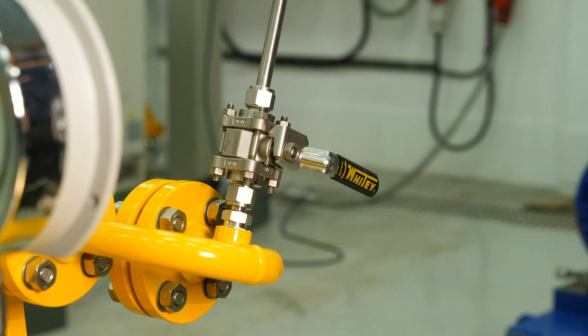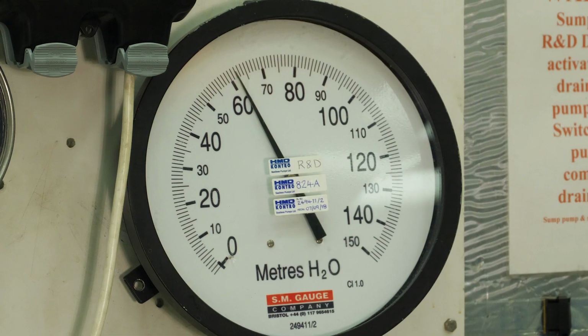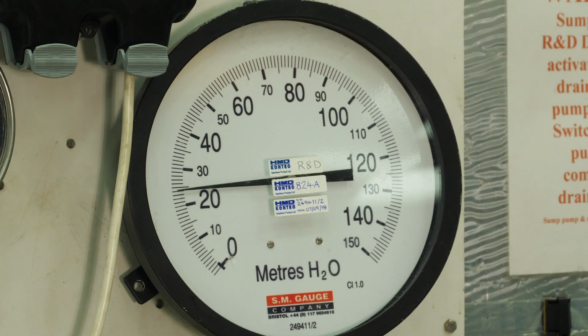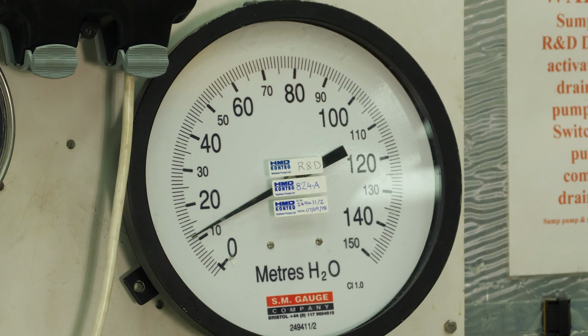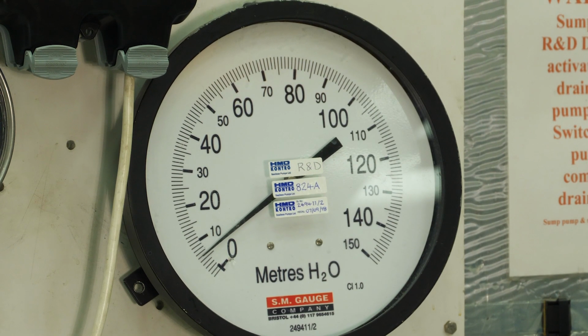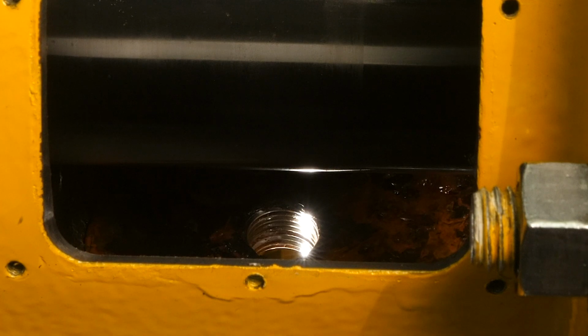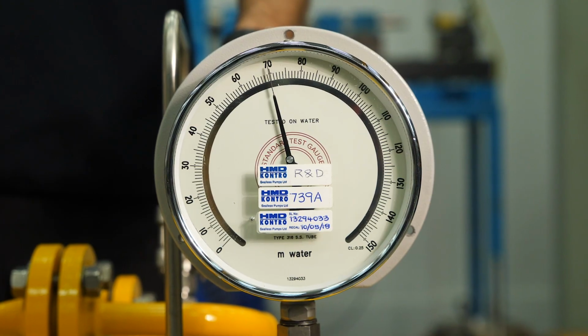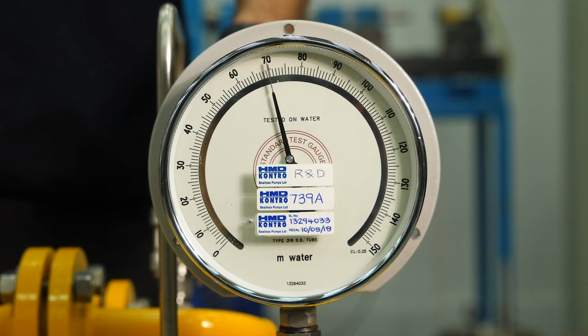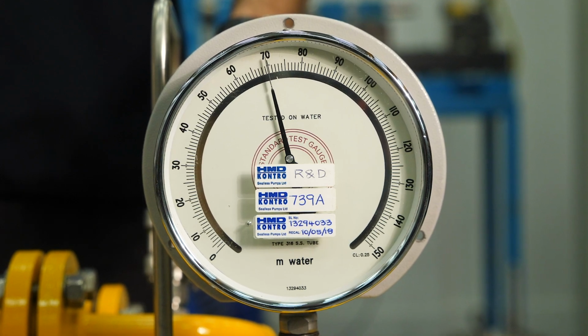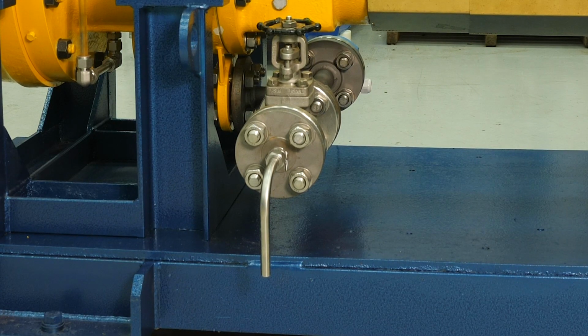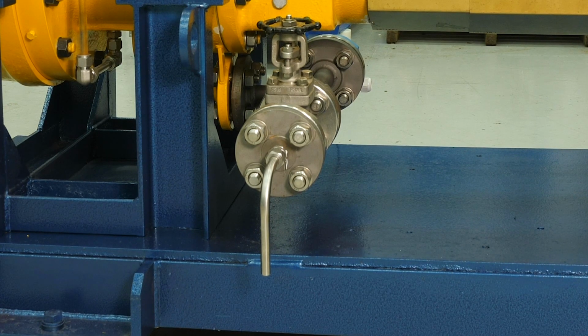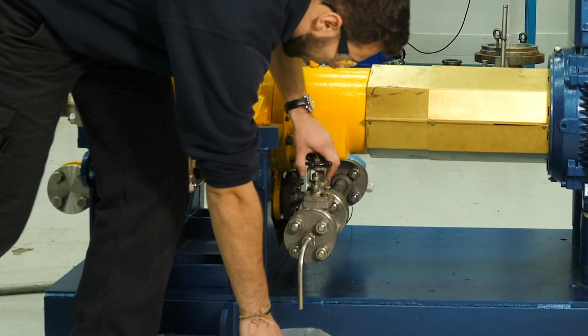Having isolated the secondary housing pressure by closing the feed pipe valve, the pump is manually switched off. When the pump has stopped rotating, the discharge pressure reduces to 0. The mechanical seal has stopped rotating with the pump, and no leakage is evident from the bearing housing drain. The system pressure and process liquid is contained. After a period of time, with the system pressure contained in the secondary pressure housing, the pressure is relieved.